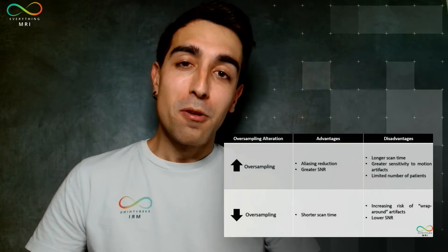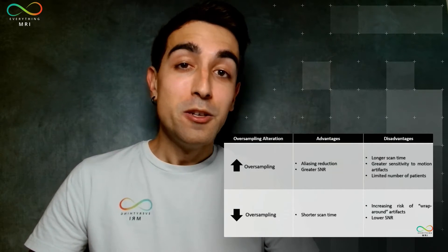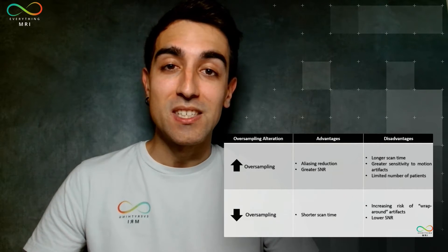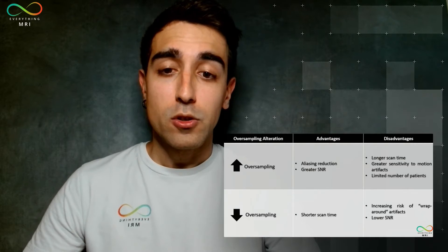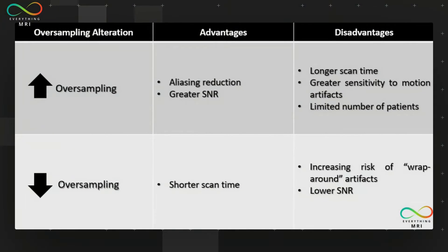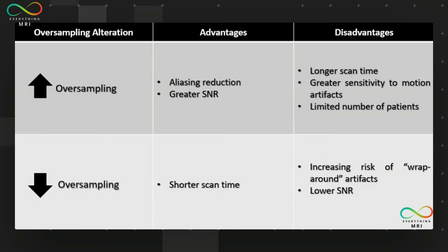For those that have been following Everything MRI for a while, you know every good story has its potential downside and oversampling is no exception. I mean don't get me wrong, as we're going to see now from our usual table of advantages and disadvantages, increasing the oversampling can be indeed a positive action and it has a lot of advantages. Along with reducing the aliasing as we have explained, it enhances the SNR by capturing additional data points beyond the FOV, enabling the MR system to better distinguish signal from noise.